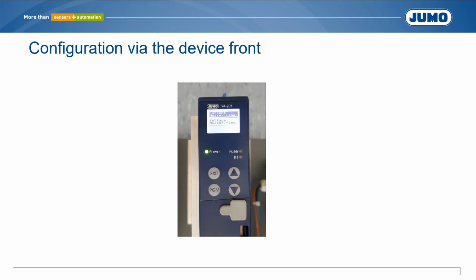The current input is used for setpoint setting. With a current signal of 20 mA, a maximum voltage of 24 volt is output. The power controller is used in phase angle control and the subordinate control is U².